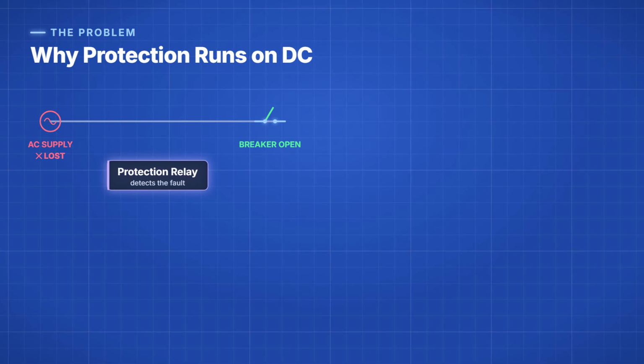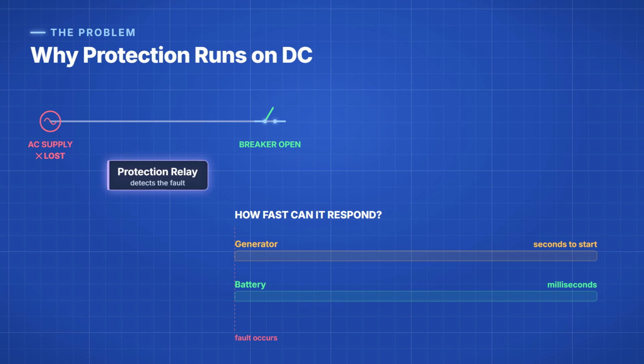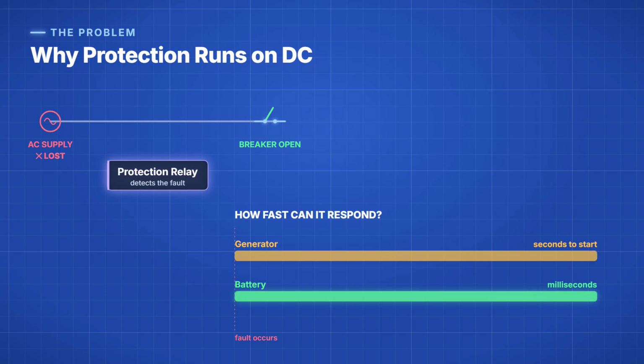Now, you might wonder why we don't just use a backup generator. The reason is time. A generator takes seconds to start, but a fault happens in milliseconds. A battery is the only power source fast enough to react instantly. So the answer is to run all of this critical control on direct current, which we shorten to DC. DC can be stored in a battery and delivered the instant it's required, whether the grid is alive or not.